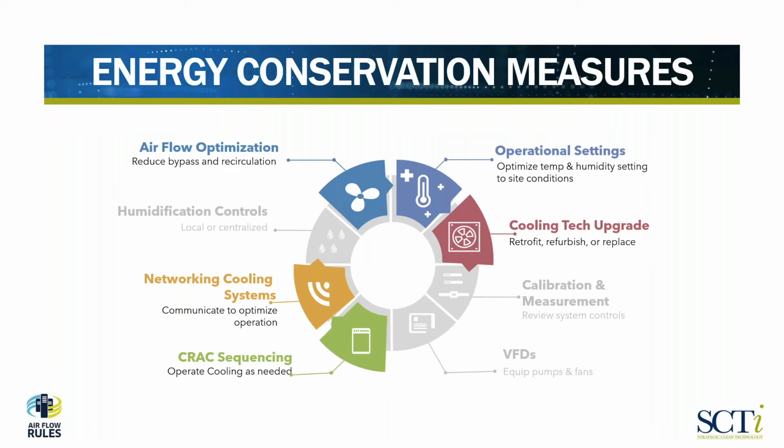And in many cases, we've gone in and done work in data centers, and when we walk in, they are operating with 8 cooling units. The customer believes they have cooling problems in that data center. They're looking at purchasing another CRAC unit in order to add more cooling. And by the time we're done with our cooling optimization program, we can show that customer that site can clearly operate, and operate much better, on 5 CRAC units or maybe even 4 CRAC units, which means that they don't incur that additional cost for new capital equipment, and they've also saved a considerable amount of money.